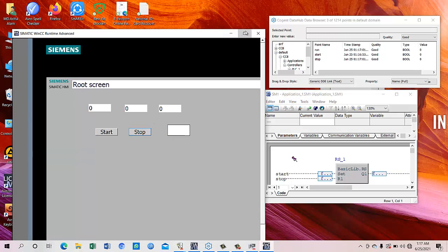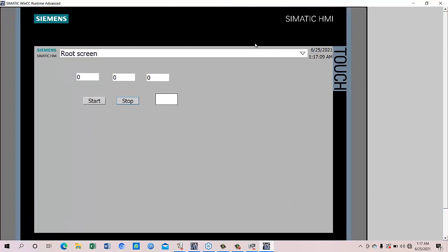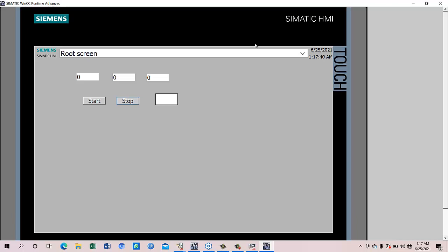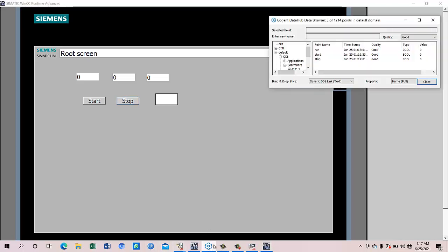Typically TIA Portal, the TP1200 device can receive bit, can receive tag connections from the OPC UA server. But if we have OPC server DA server, then we have to convert from OPC DA to OPC UA. Then we can connect to HMI. But here everything is in the local host. That means the runtime, TIA Portal runtime is on my laptop. The soft controller and the AC 800M controller is also in my laptop. And also the Cogent Data Hub is also in the laptop. And everything that the Cogent Data Hub is communicating from the local host. But I think it can communicate over TCP IP also.